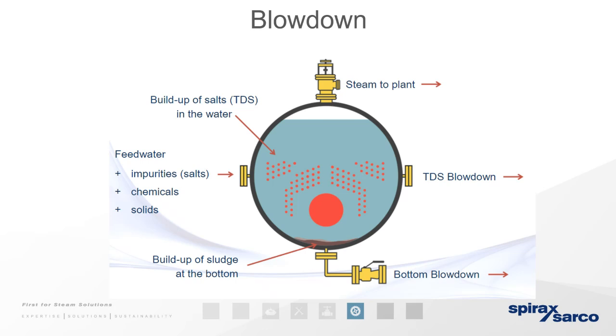So here, blowdown. Why do we blow down? So in addition to level controls, pumps, alarms, all those kinds of things, we also need to test and blow down the boiler, which means maintaining the correct water chemistry within the boiler. When you end up with sludge at the bottom of a boiler, not only is that displacing the amount of water you can have in the system, but it floats around the system. It doesn't always sink to the bottom. It coats fire tubes, pass tubes, lowers their ability to transfer heat. So we regularly blow down a boiler. I think it's either once a day or once per shift that is recommended.